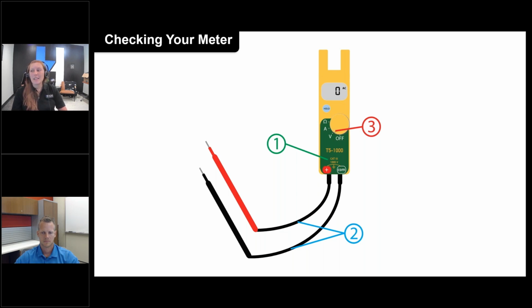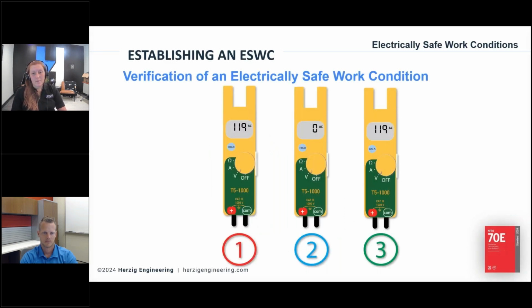And it seems kind of silly, but number 3 is pointing to the dial there. It's got 3 options and an off. Make sure it's on the right setting. It really is so easy to accidentally turn it one setting too far. Or on the other hand, you have some pretty complex meters out there with a bunch of functionality and a bunch of buttons, and it's really easy to fat finger it and end up on the wrong setting. If you put leads on equipment on the wrong setting, it could cause problems. Maybe it would just damage your meter, but maybe worse. So make sure you've got the right tool for the job and then do that live, dead, live check.